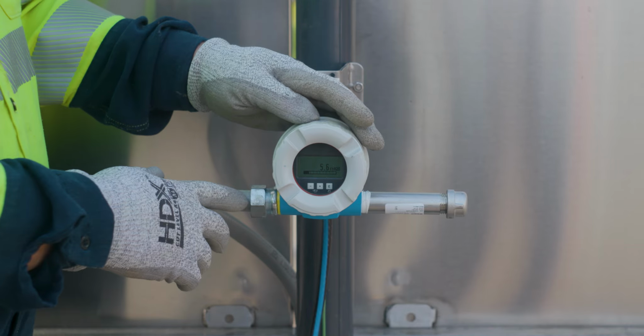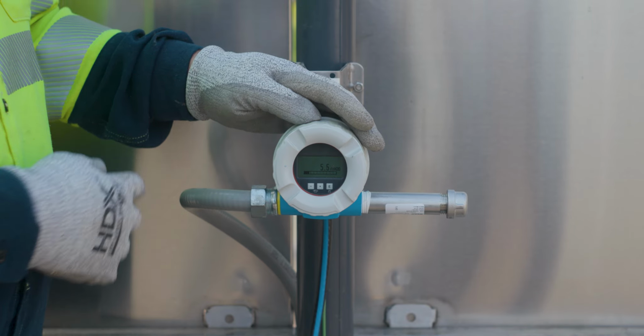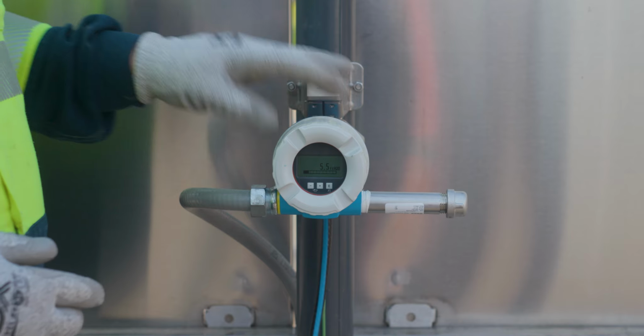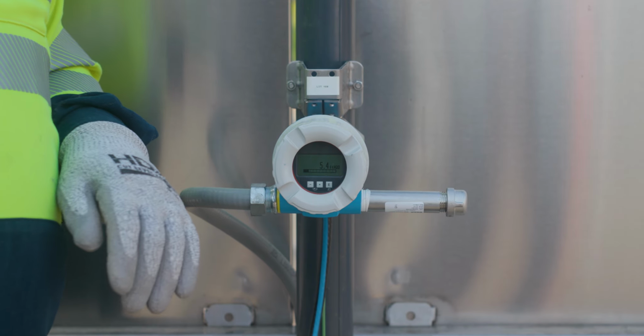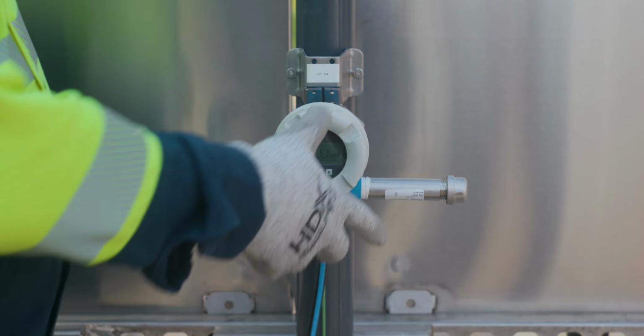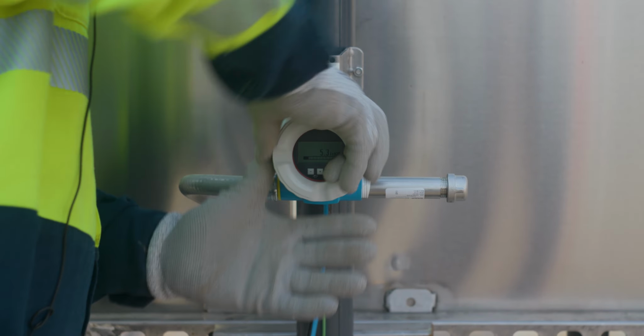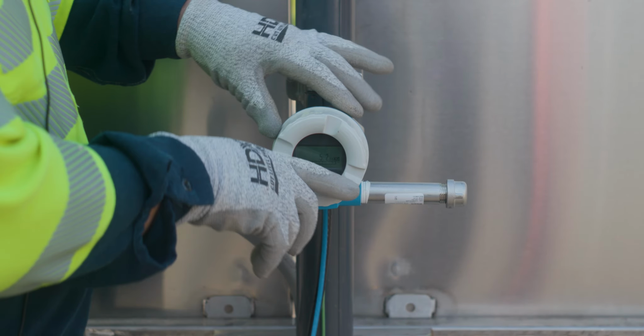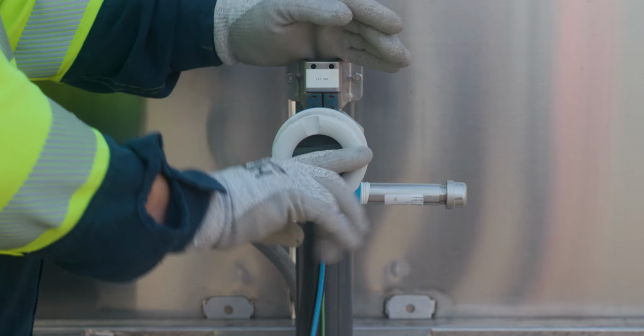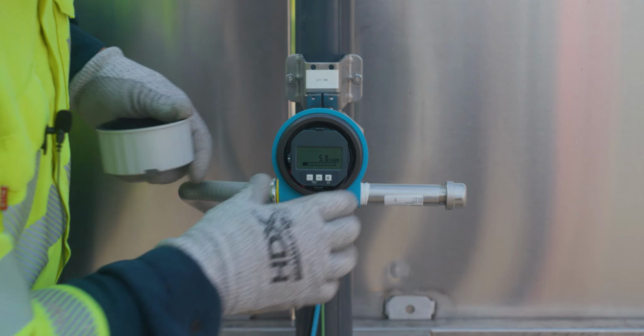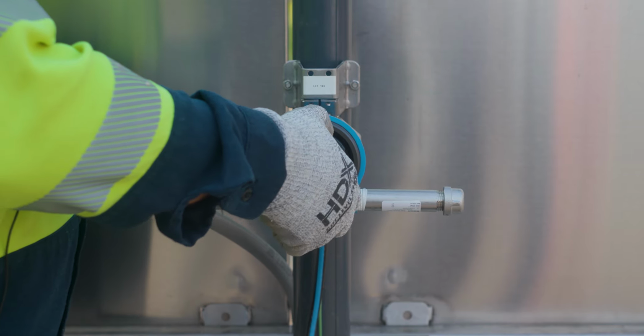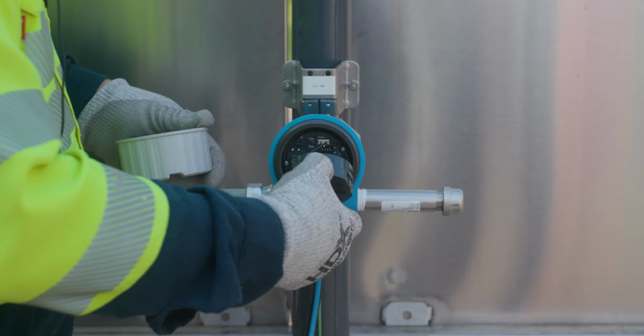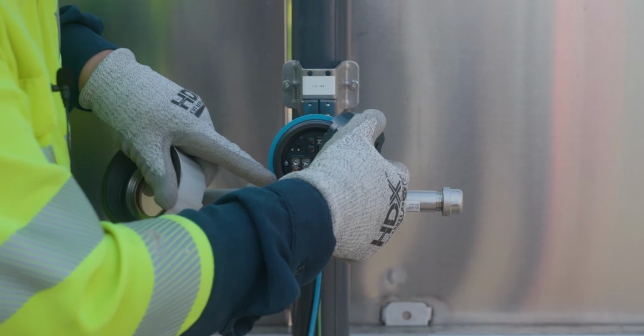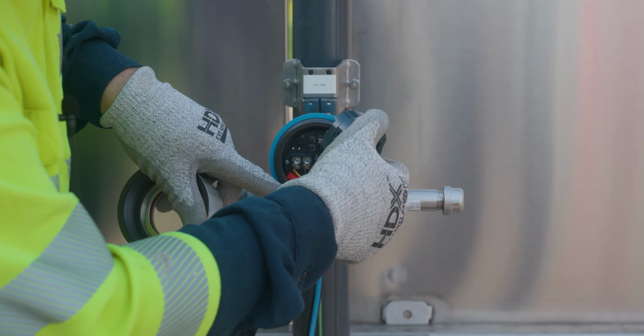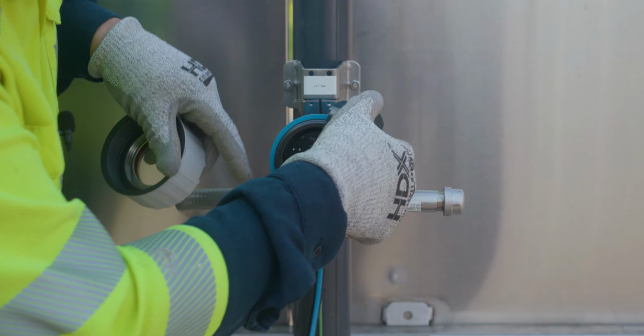It only uses a shielded cable to communicate from here. It transmits from here to the PLC, and the PLC reads that difference. It's an aluminum cover. It unscrews. If it's too tight, you can use a screwdriver across these to loosen it.